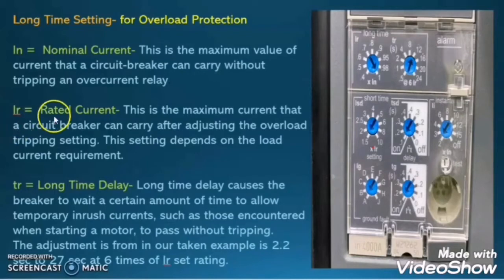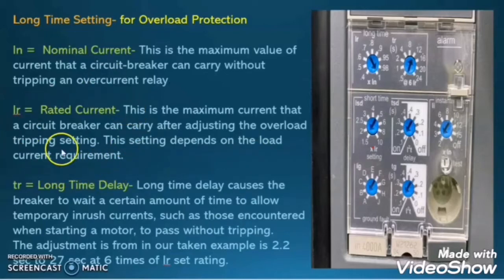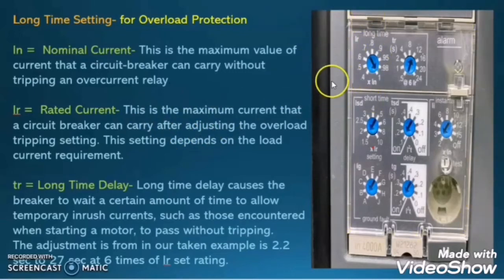What is IR? IR is the rated current. This is the maximum current that the circuit breaker can carry after adjusting the overload tripping setting, and this setting depends on the load current requirement. It means the maximum current that the circuit breaker can handle for normal operation when the overcurrent tripping setting is adjusted.